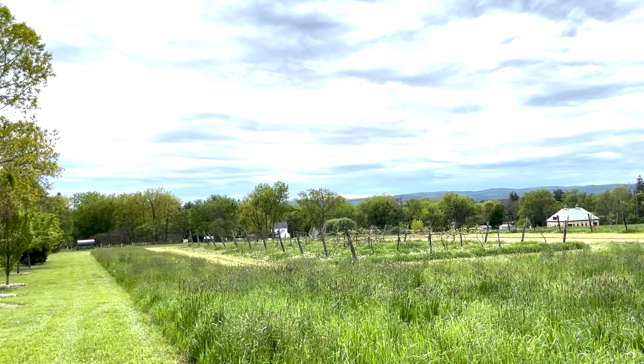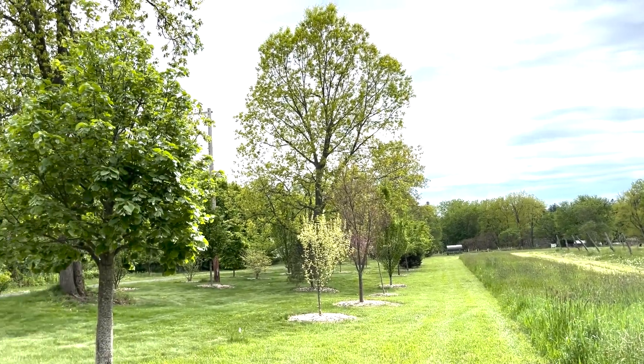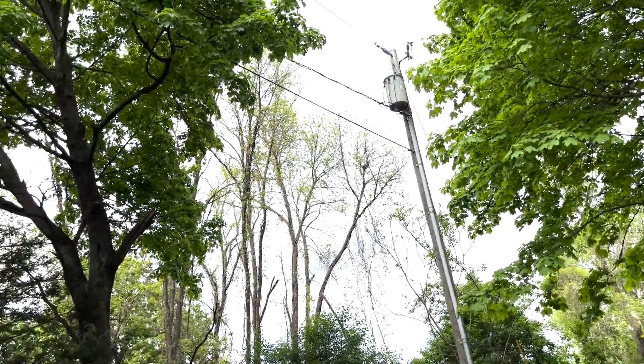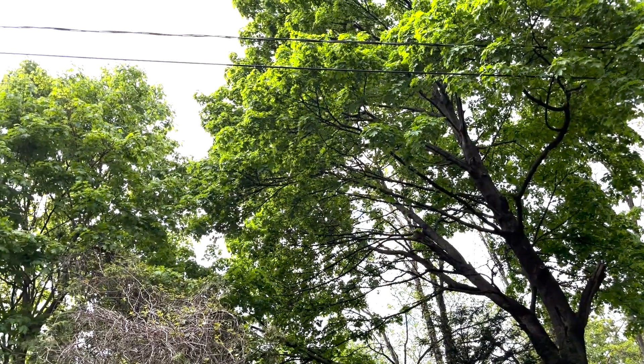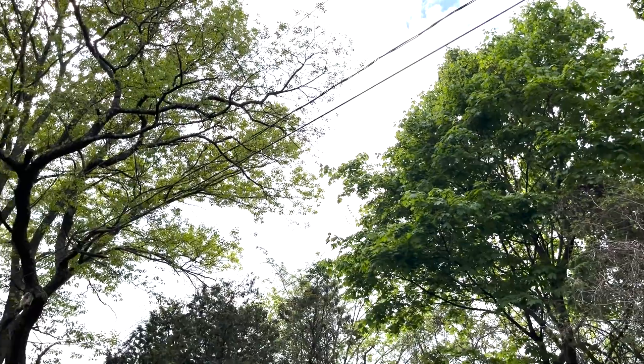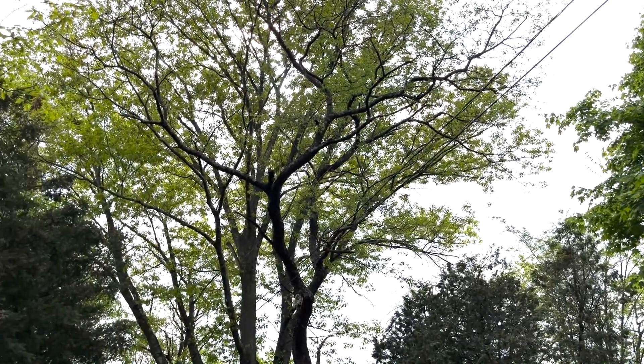So if there's a mature tree that we're trying to keep, or a tree warden wants to save and not trim as much, there are some options up there on the top of the pole that you can see what we can do — as opposed to just a basic cross arm. We could put an alley arm on, which is just to one side or the other. We could shift it to a spacer cable, which is a bundle of the wires. Pretty cool stuff at UMass — we don't have that anywhere else.